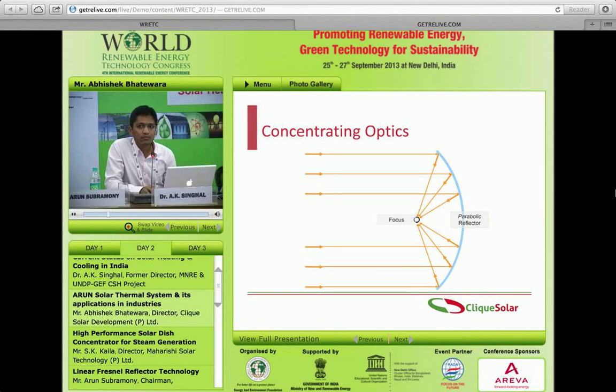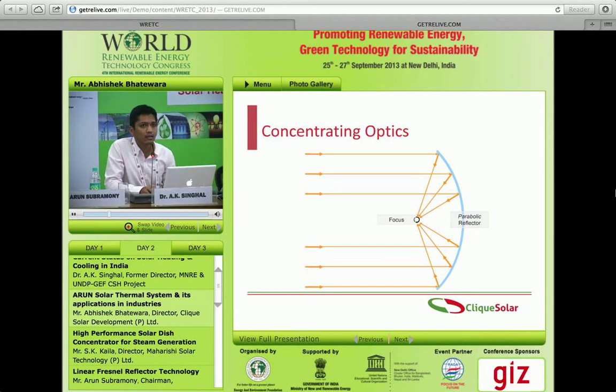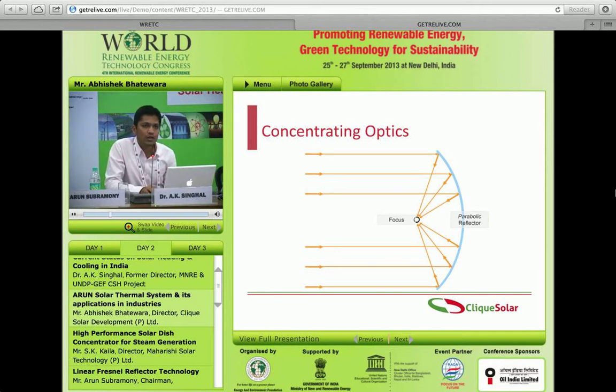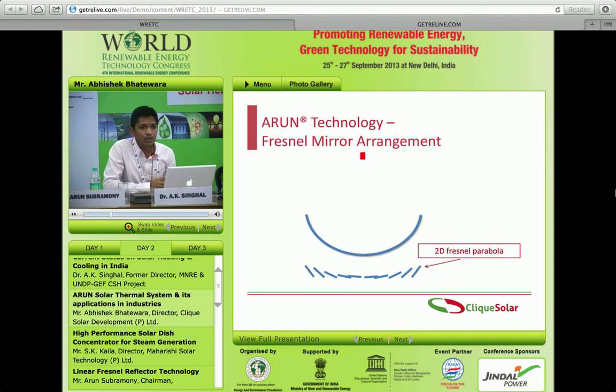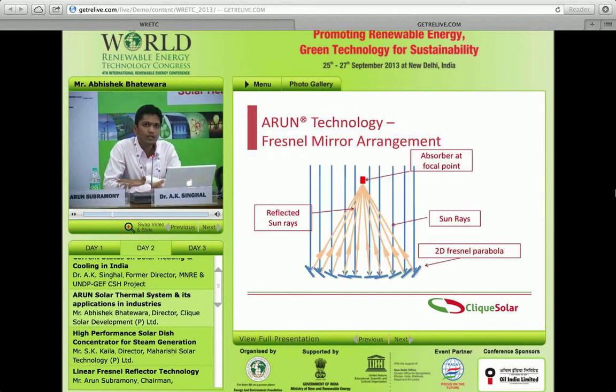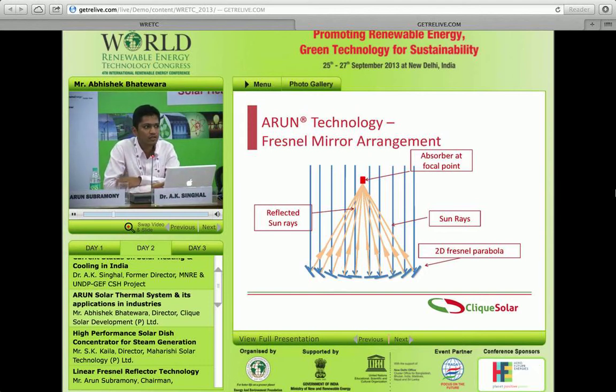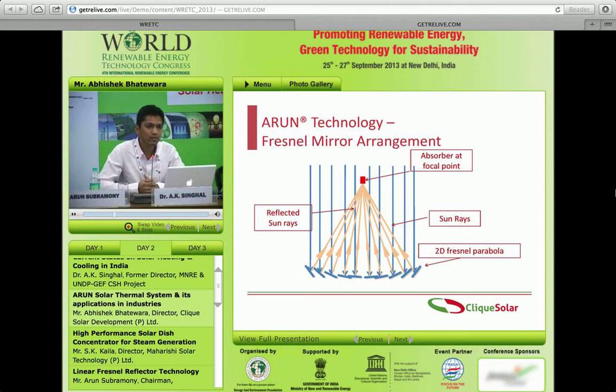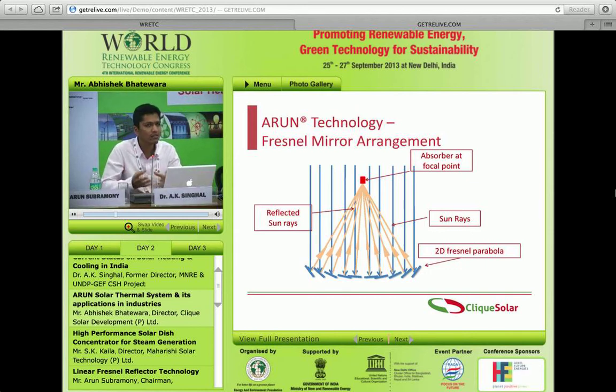The basic principle involves a parabola. The focus of a parabola is such that anything perpendicular to the surface will get focused at that focal point. In Arun technology, you Fresnelize the parabola — meaning you cut it into small pieces. Manufacturing a continuous parabolic surface of 14 meters in diameter is difficult, the accuracy is hard to achieve, and transportation is impossible. So you digitize it — cut it into small pieces and arrange them to give that 3D parabolic effect.